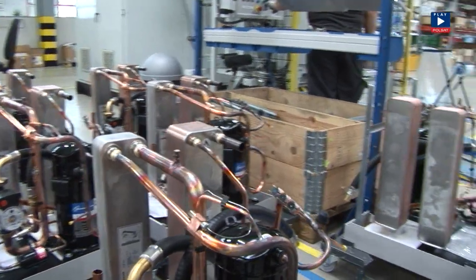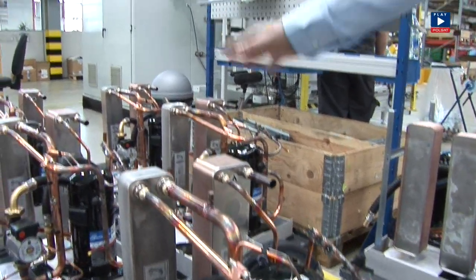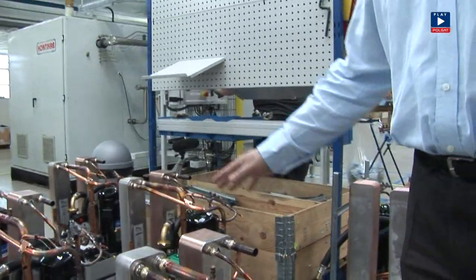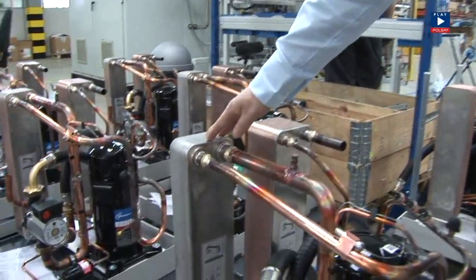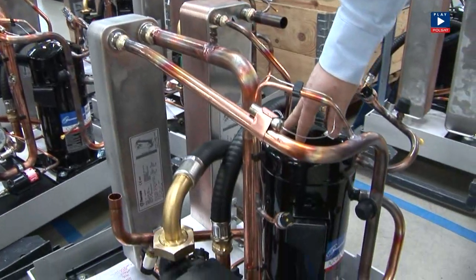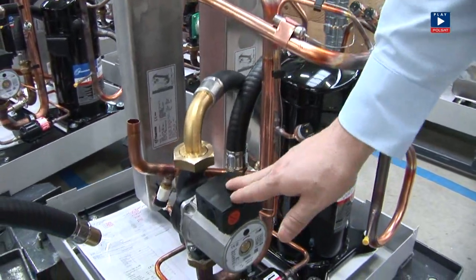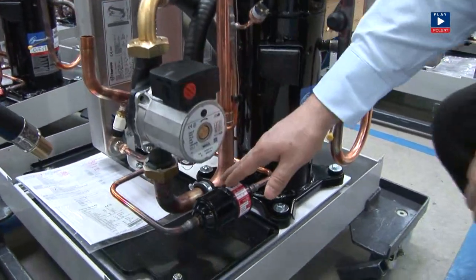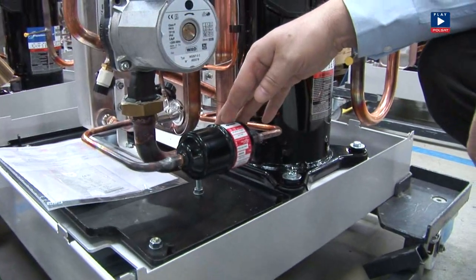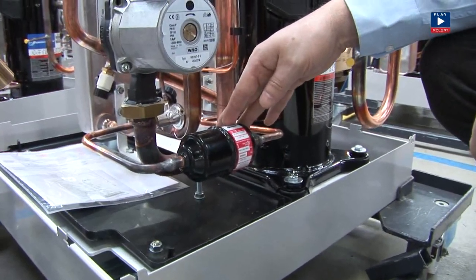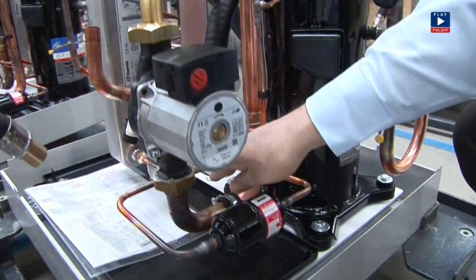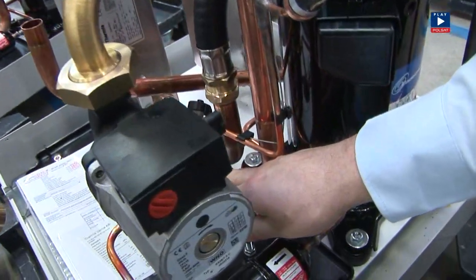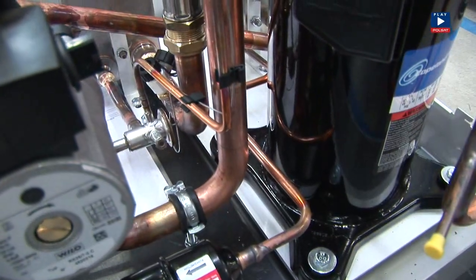The key elements of a heat pump. Here we can see a complete ensemble heat pump. Those are heat exchangers. This is the compressor, of course the circulating pumps. A filter which maintains the quality of the refrigerant. And the expansion valve which regulates the pressure and the temperature of the refrigerant in order to maintain the constant cycle. This is why we often call it the heart of the heat pump.